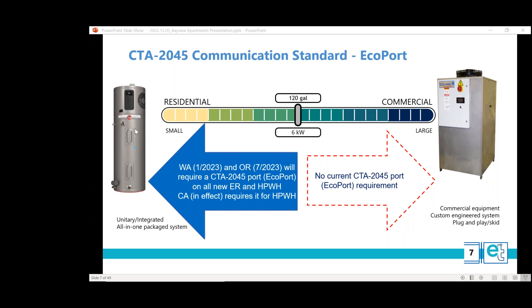The CTA 2045 requirement applies to resistance tanks and heat pump tanks of the residential kind — specifically 120 gallons and less. Larger systems are not required. In Washington it takes effect January 2023, in Oregon next July, and in California it's currently in effect for heat pump water heaters. Though not required on large tanks, they did get a port into the Bayview project.